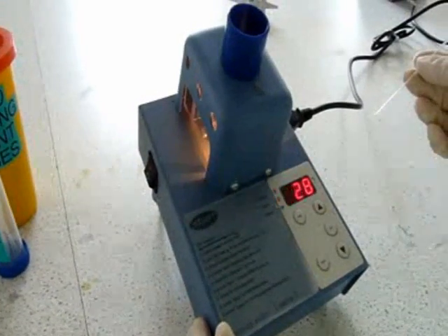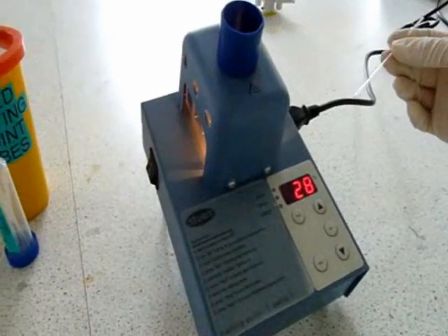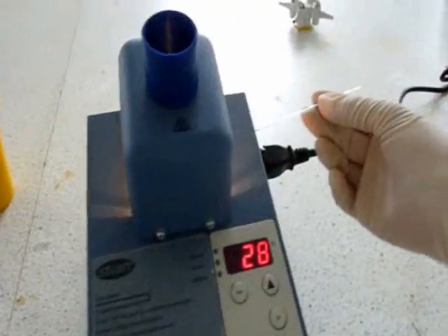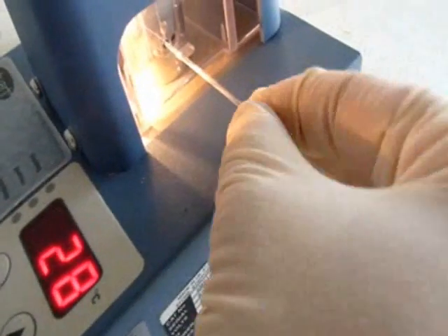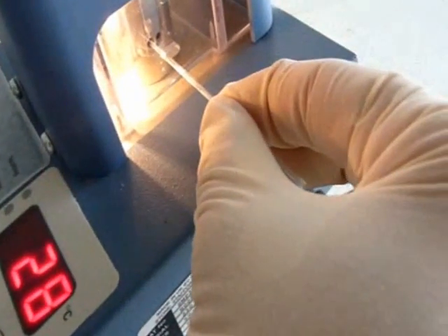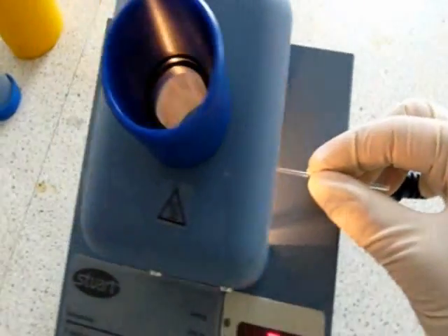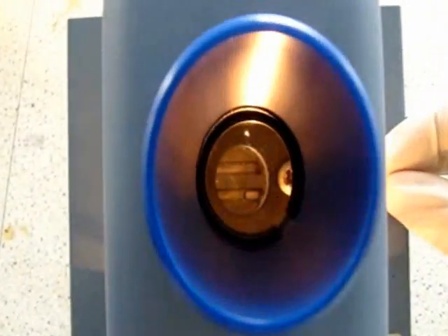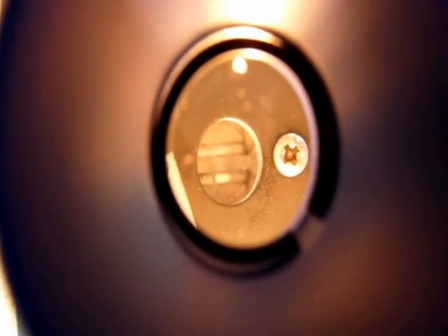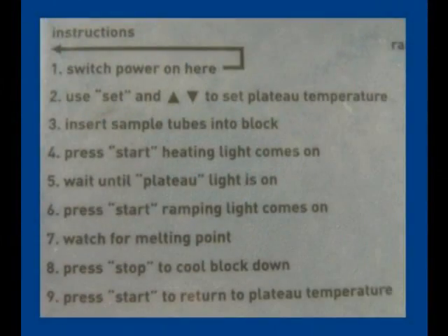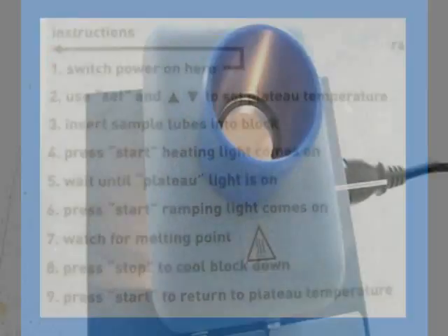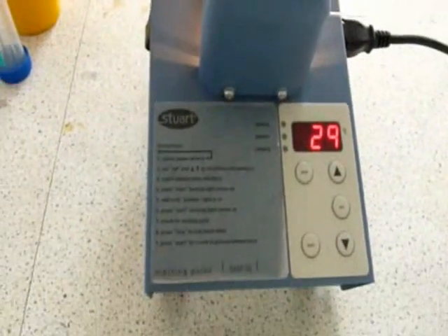Turn the melting point apparatus on. Place the capillary in the melting point apparatus and ensure that the sample is visible through the viewfinder. Never put the open end into the apparatus. Now follow the instructions printed on the side of the melting point apparatus.